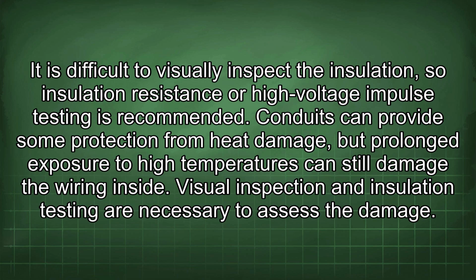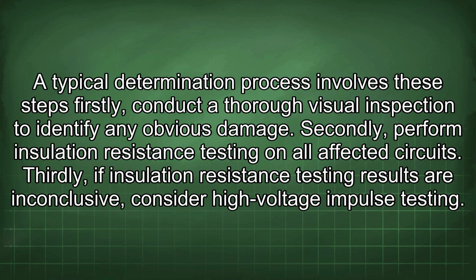Conduits can provide some protection from heat damage, but prolonged exposure to high temperatures can still damage the wiring inside. Visual inspection and insulation testing are necessary to assess the damage. A typical determination process involves these steps.